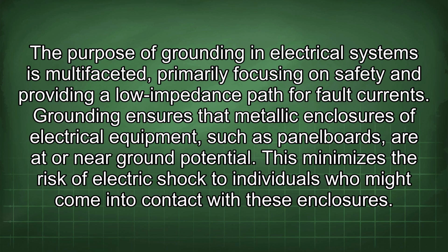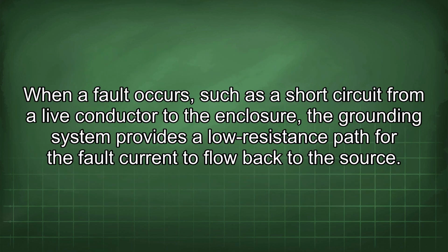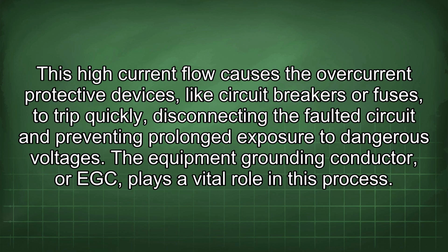The purpose of grounding in electrical systems is multifaceted, primarily focusing on safety and providing a low-impedance path for fault currents. Grounding ensures that metallic enclosures of electrical equipment, such as panel boards, are at or near ground potential. This minimizes the risk of electric shock to individuals who might come into contact with these enclosures. When a fault occurs, such as a short circuit from a live conductor to the enclosure, the grounding system provides a low resistance path for the fault current to flow back to the source. This high current flow causes the overcurrent protective devices, like circuit breakers or fuses, to trip quickly, disconnecting the faulted circuit and preventing prolonged exposure to dangerous voltages.